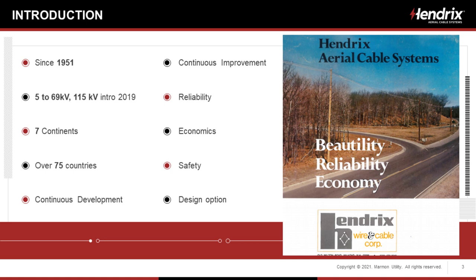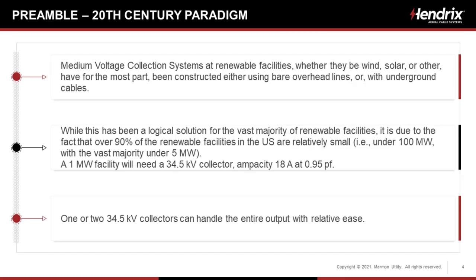Quick intro. We've been around since 1951. Spacer cable is not new. We started with 5, 15, 25, 35, 46, and 69 kV. We've been in 69 for over 25 years, and we introduced 115 kV in 2019. We're on all seven continents, including Antarctica, in over 75 countries. It's a company with continuous development, continuous R&D, and continuous improvement, and we're installed for reliability, economics, and safety. Again, we say it's not for everywhere, but it is a design option that has benefits in certain applications.